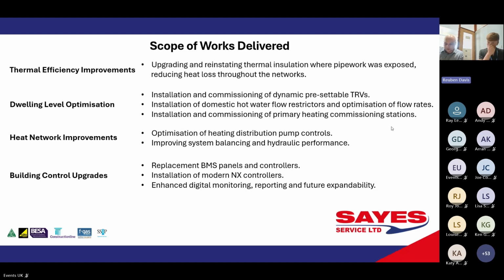Within the individual dwellings, we delivered a series of optimisation measures, including the installation and commissioning of dynamic presettable TRVs, domestic hot water flow restrictors, and primary heating commissioning stations. Alongside this, we reviewed and optimised pump controls to improve hydraulic performance and system balancing throughout the buildings. We also carried out substantial building controls upgrades, replacing the heating controls equipment and installing modern web-enabled NX controllers. This provides Connect Housing with a much more capable and expandable controls platform, along with enhanced visibility of system operation and performance. Importantly, these measures weren't delivered in isolation - each improvement was designed to complement the others, creating a more efficient, controllable and better performing heating system as a whole. Next slide, please.